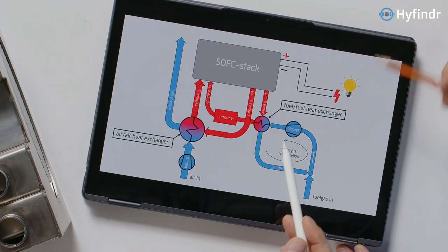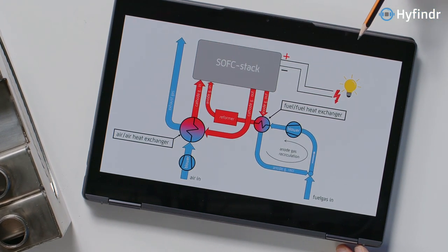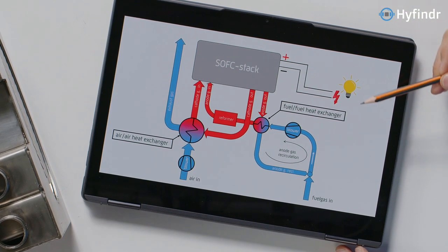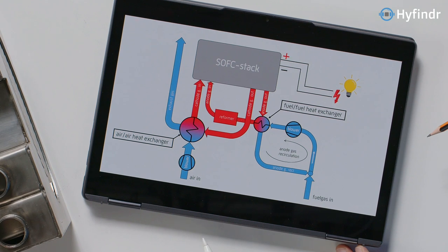When you go through these heat exchangers, you can see the blowers in the scheme. The blowers need electric energy, and this reduces the overall efficiency of the entire system. Because of this, it's necessary that the pressure drop inside of these heat exchangers is very low.